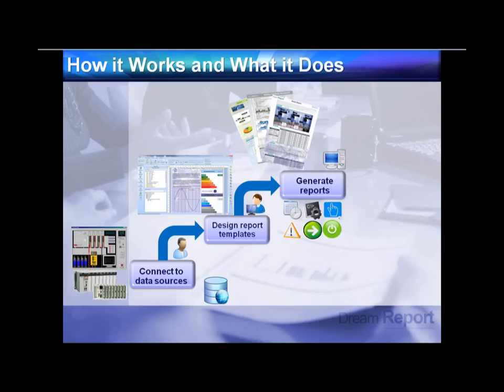You then determine how reports are generated: on a schedule (daily, weekly, every shift), by a command line — for example, an HMI firing off a command to generate a specific batch report with a specific batch ID — or event-based, such as monitoring a bit in the PLC that goes high at the end of a batch, or an analog value like run hours on a piece of equipment exceeding 1000 hours, triggering a maintenance report.